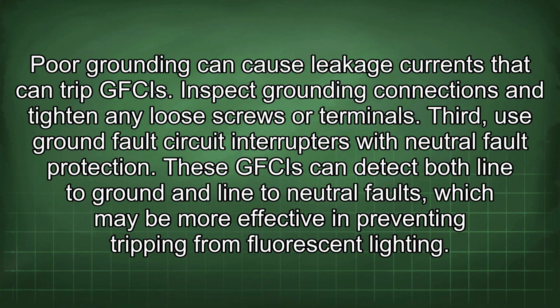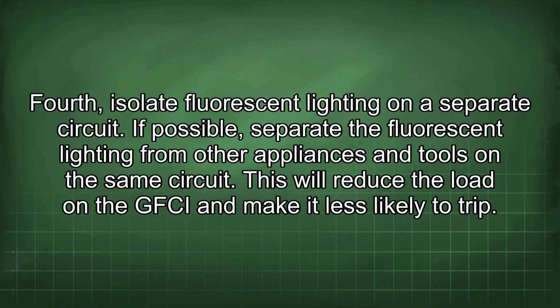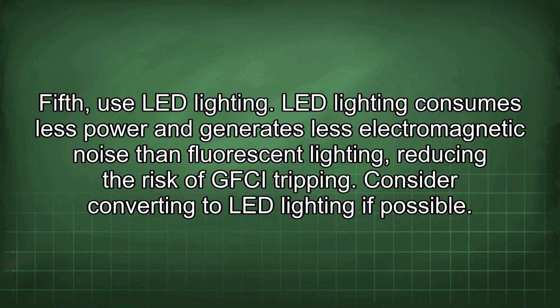Third, use ground fault circuit interrupters with neutral fault protection. These GFCIs can detect both line-to-ground and line-to-neutral faults, which may be more effective in preventing tripping from fluorescent lighting. Fourth, isolate fluorescent lighting on a separate circuit. If possible, separate the fluorescent lighting from other appliances and tools on the same circuit. This will reduce the load on the GFCI and make it less likely to trip. Fifth, use LED lighting. LED lighting consumes less power and generates less electromagnetic noise than fluorescent lighting, reducing the risk of GFCI tripping. Consider converting to LED lighting if possible.